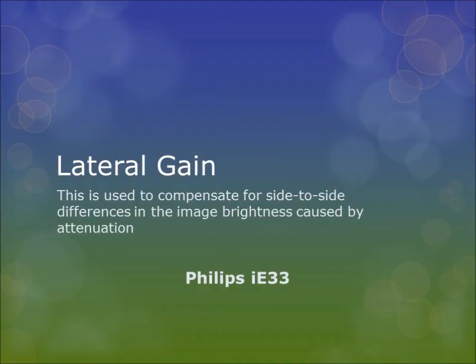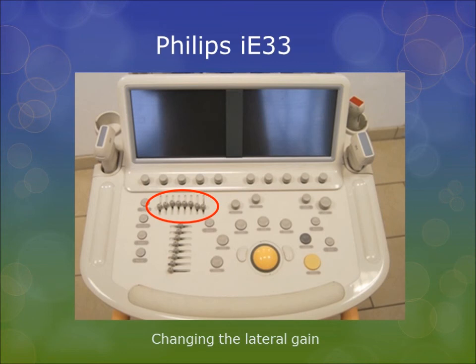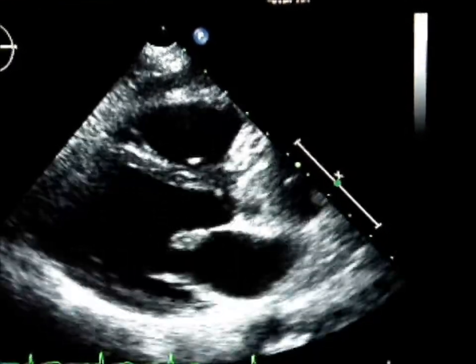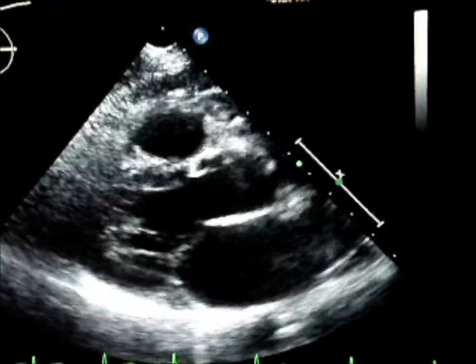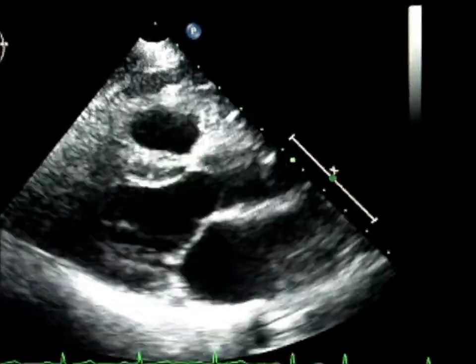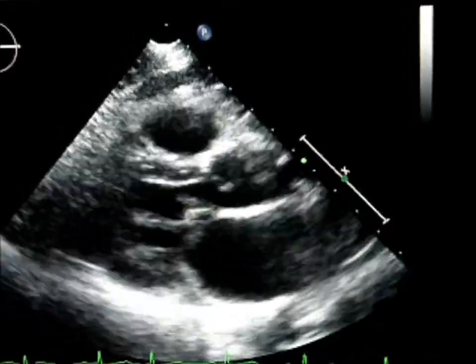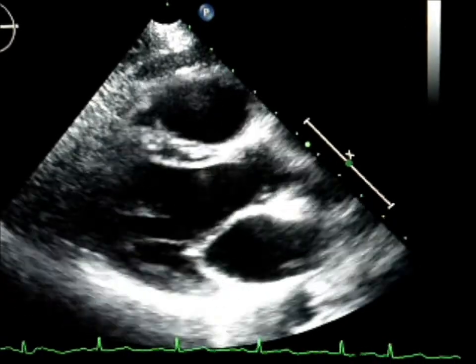Lateral gain is used to compensate for side-to-side differences in image brightness caused by attenuation. Much like TGC, each lateral gain bar affects the amount of gain across the screen vertically from left to right. The machine used to demonstrate this is the Philips IE33.